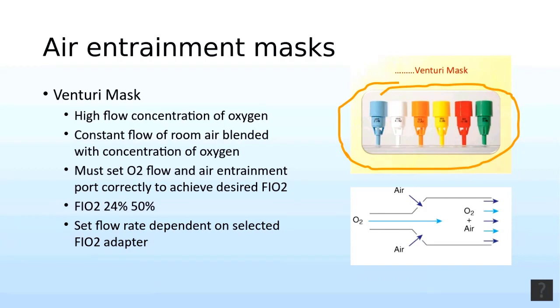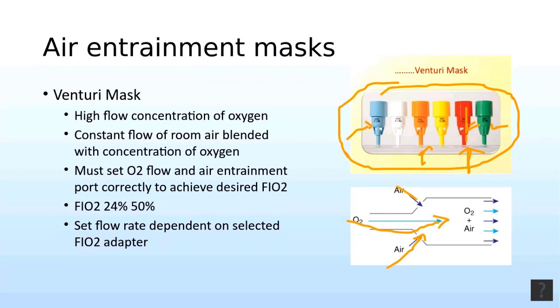Notice these openings right over here at the base of the device. You can see that the openings are variable, and they are designed to allow ambient air to mix with the oxygen coming from the wall. So the oxygen coming from the wall goes in here, air also mixes here, and then the desired concentration is achieved. The flow of oxygen from the wall mixes with air through these openings, and that corresponding mixture is delivered to the patient.